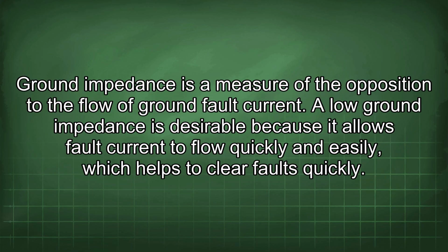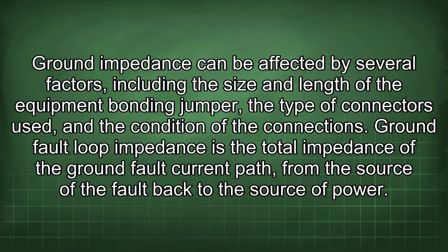Ground impedance is a measure of the opposition to the flow of ground fault current. A low ground impedance is desirable because it allows fault current to flow quickly and easily, which helps to clear faults quickly. Ground impedance can be affected by several factors, including the size and length of the equipment bonding jumper, the type of connectors used, and the condition of the connections.